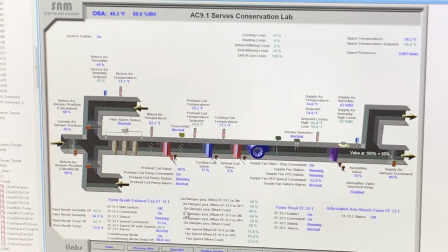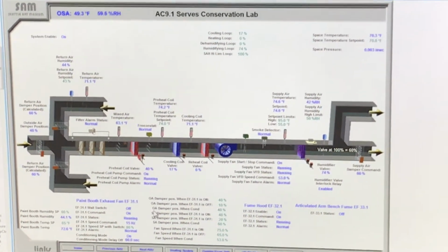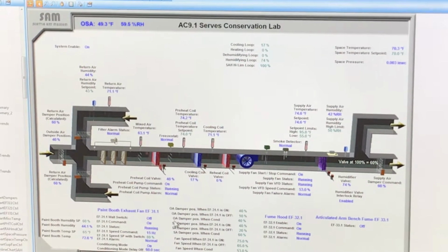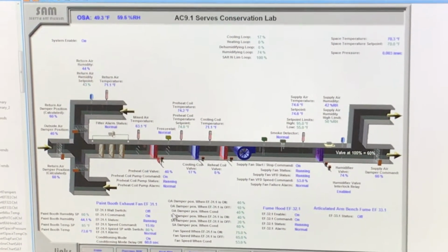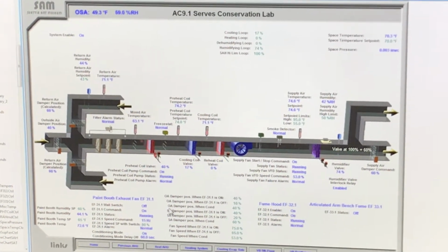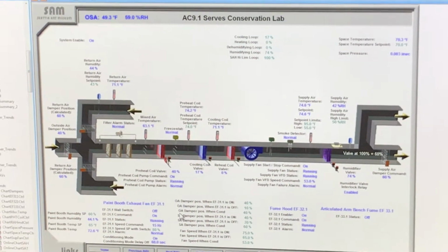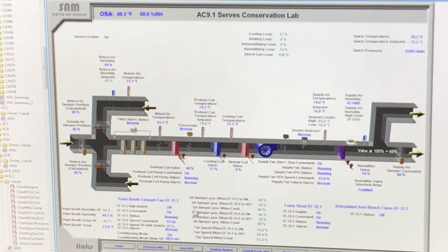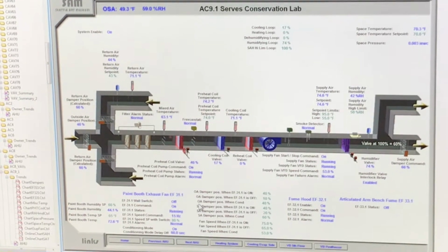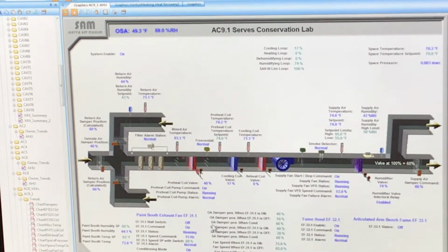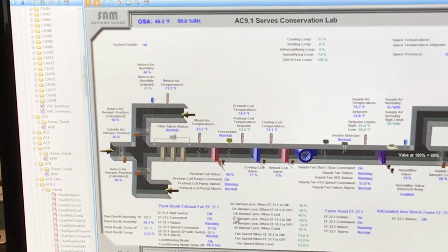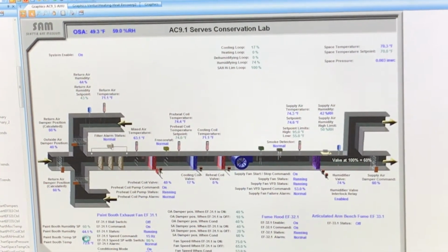All the values here, they have the supply air damper, the outside air damper, the fan speed, and the exhaust fan speed. The balancing guy is trying to set those values so that in different conditions the area will be maintained slightly negative or negative. So those values are already balanced and should not really be adjusted.